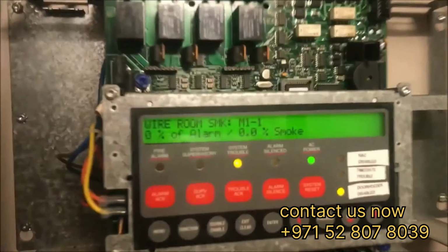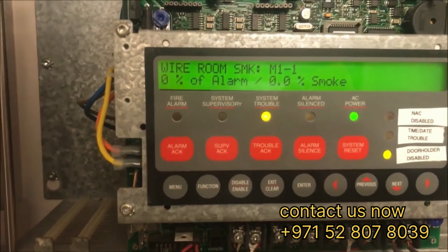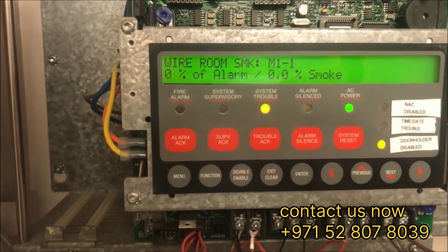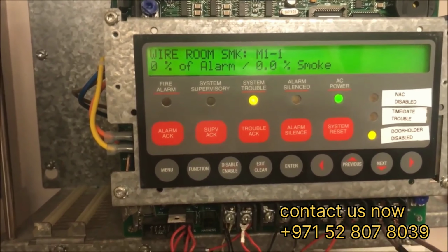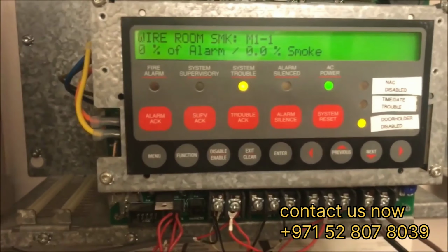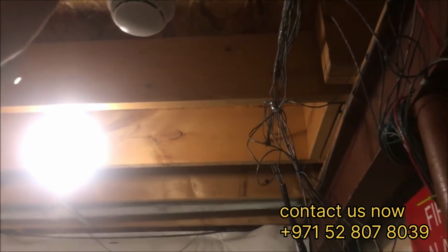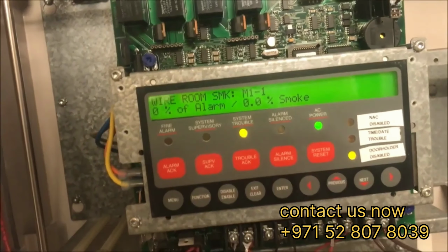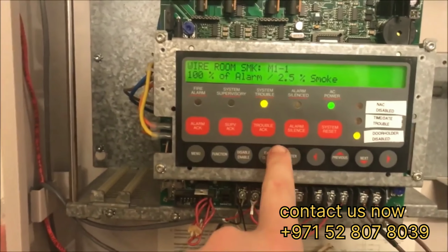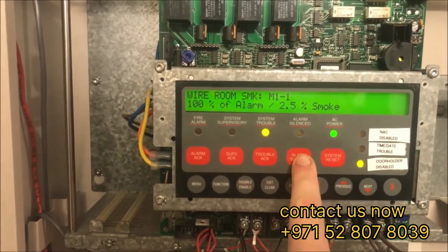But if I go and shoot a little Solo into it, this will make the values, hopefully I got enough in there, start to jump up. I talked about this, I think, with the heat detector in a video. It was like cool Simplex heat detector or something. It may not have gotten enough in there to register. But you can go in and see the current status of a smoke detector and read it in real time. Hope it's not going to alarm. Crap, I got too much in there.